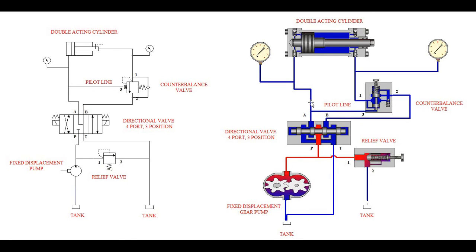The other two positions of this spool are much easier to visualize when we get to part two of this tutorial when we bring the animated circuits into it. But for now, what you would have to envision is if this spool shifts to the left here, this pressure coming in at the P port would actually be exposed to the A port. If you can envision this spool shifting over, that correlates with this position right here with P going to A.